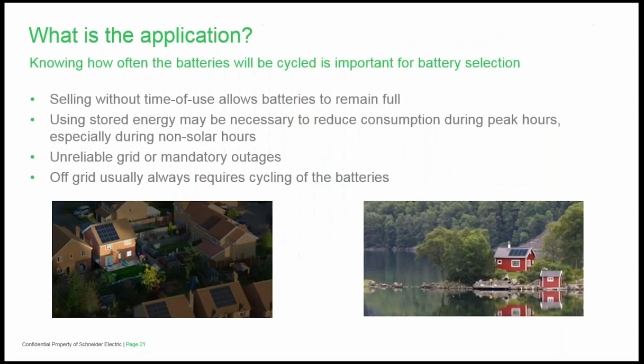So now shifting to application. When we're designing a system, the goal of the customer should be recognized early in the design phase, which will determine the delta of daily storage requirement. If a customer merely wants to support the loads during solar hours and sell any excess, then the batteries can remain full. The days of autonomy should be considered if it's significant to the customer, typically more important in regions that are susceptible to storms in the United States.